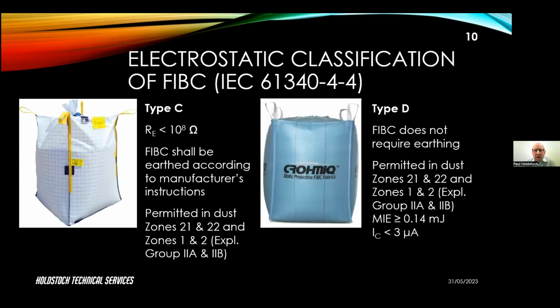If you want to use an FIBC in a gas zone as well as a dust zone, so in zones 21 and 22, then you need full static protection, and this is provided either by a type C, or conductive, FIBC, or the type D. So the type C, these are typically made from fabrics containing conducting threads, and the resistance to earth from any point on the bag needs to be less than 10 to the 8 ohm. The important point is that the FIBC shall be earthed according to the manufacturer's instructions.